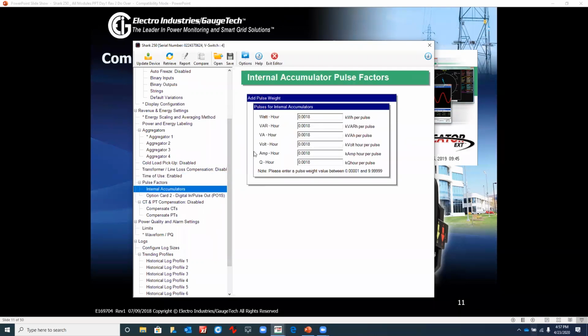Let's look at the internal accumulators. This is an area in the meter where the pulses are being recorded internally as a separate recorder, and you can retrieve the pulse data from the meter. And that's not an optional board, that's internal to the meter, and that allows you to get that information.